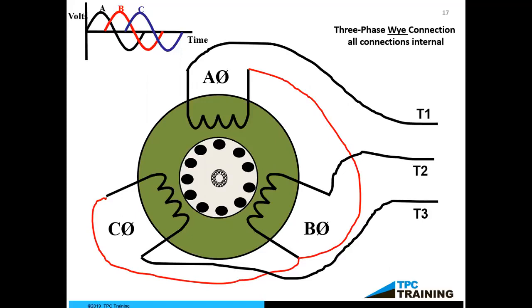So all we're doing with the ohm meter is just checking to see if our windings are good or not. And if we do see a bad reading, we know that OL, the motor won't start. We know 0 ohms, there could be an explosion. So that's one of the checks that we can see.